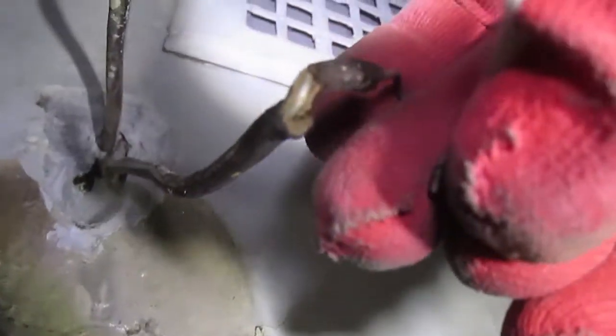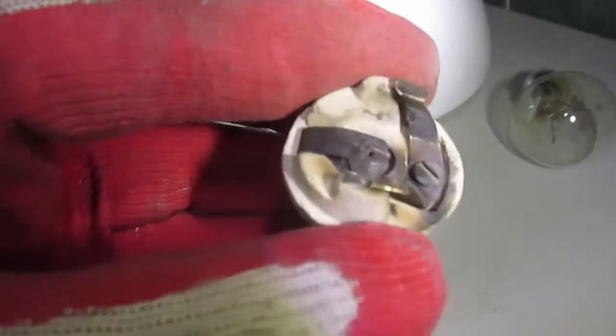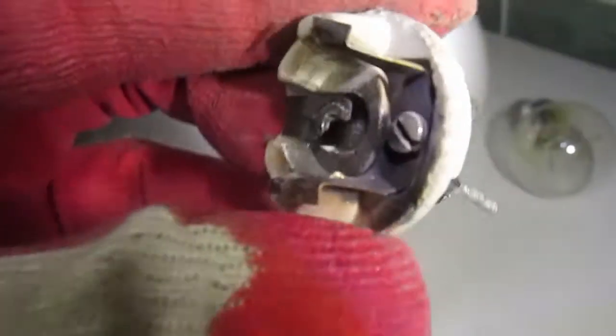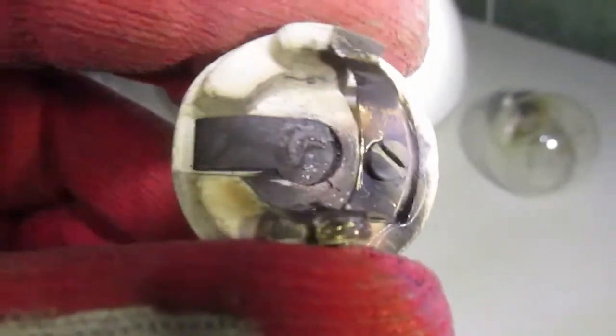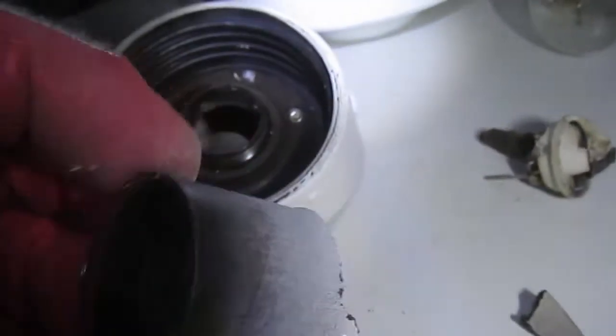By the way, in the apartment there are some more things I want to show you. The wiring in the apartment is aluminum and it is very old. The old aluminum conductors break apart inside the sheath. The old bulb holders fall apart. The estimated age of this bulb holder is between 20 and 30 years, and most of the time, if not all of it, it was working with incandescent bulbs, which were very hot. This bulb holder should have been changed a number of times in the course of these 20 to 30 years, but it was not until now. So let's go and see.